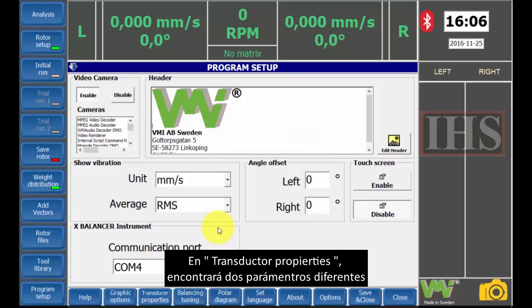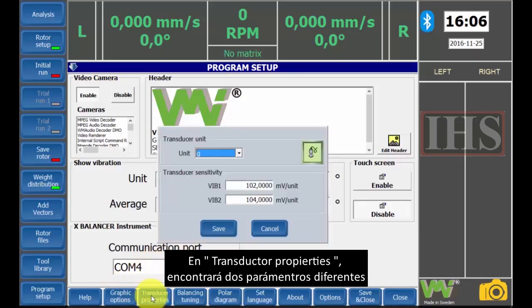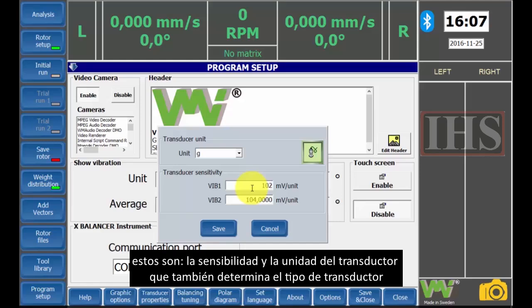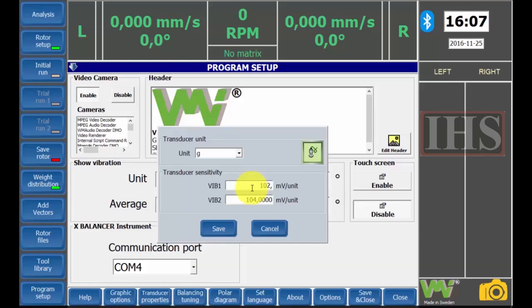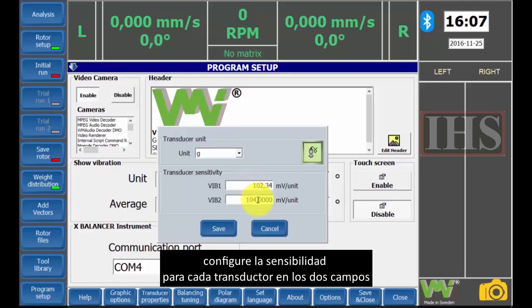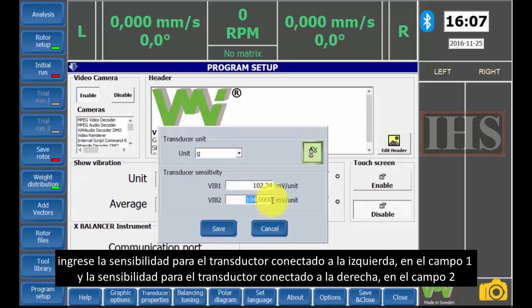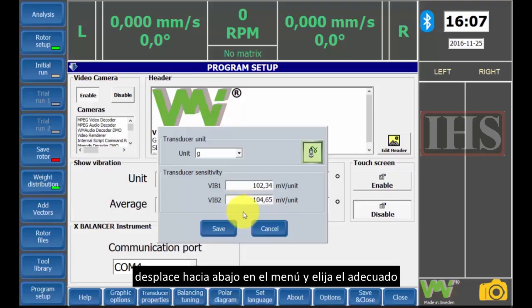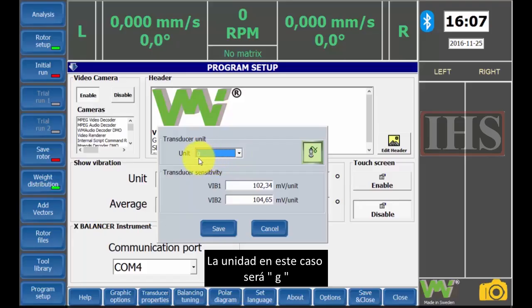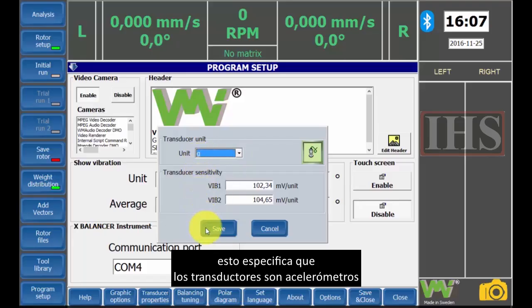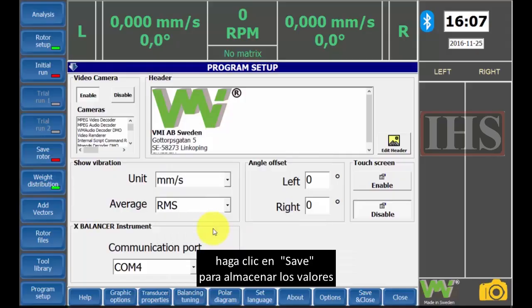In the transducer properties, you will find two different parameters. These are the transducer sensitivity and the transducer unit, which also determines the transducer type. Set the sensitivity for each transducer in the two fields. Enter the sensitivity for the transducer connected to the input marked left in the field VIB1, and the sensitivity for the transducer connected to the input right in the field VIB2. Under transducer unit, scroll down the menu and choose the proper unit. In this case, it will be G, which specifies that the transducers are accelerometers. Click Save to store the values.